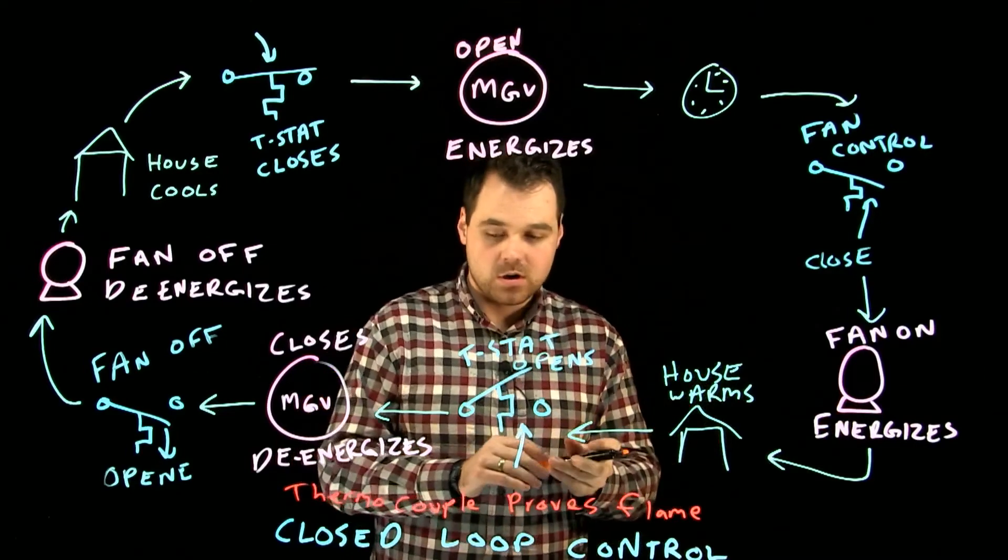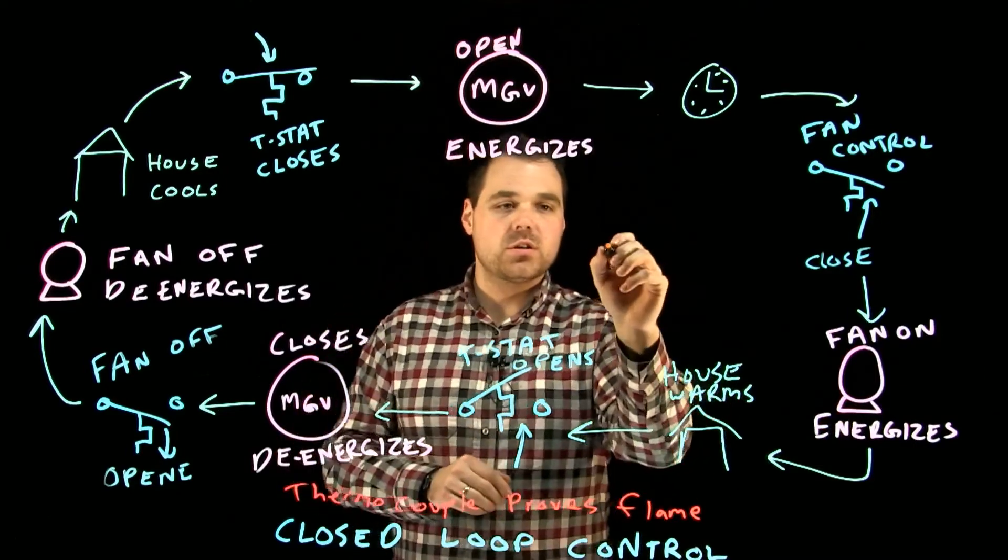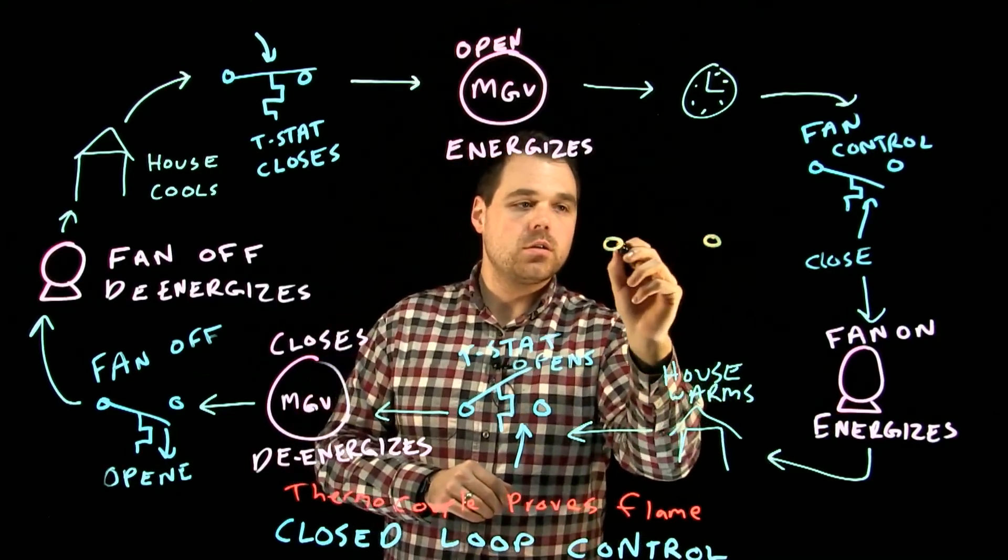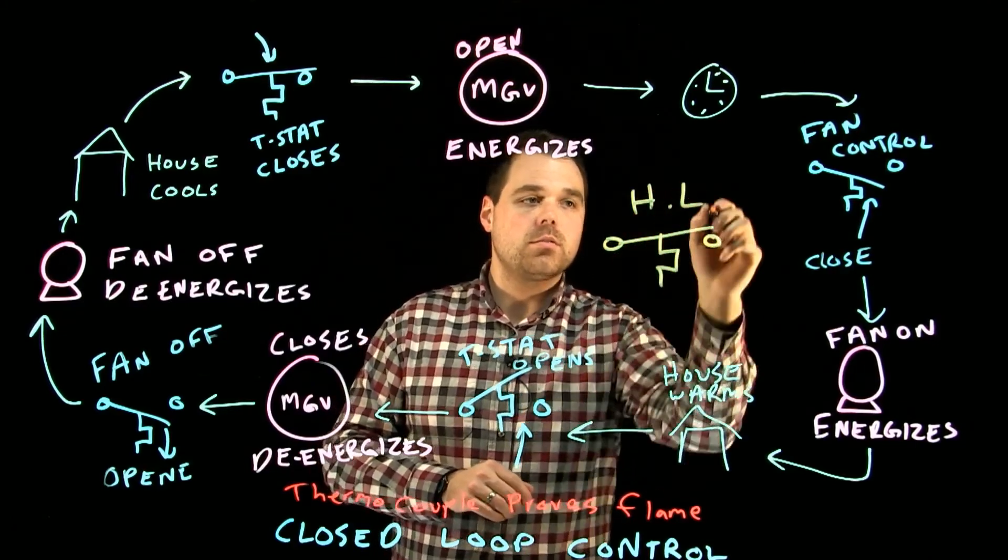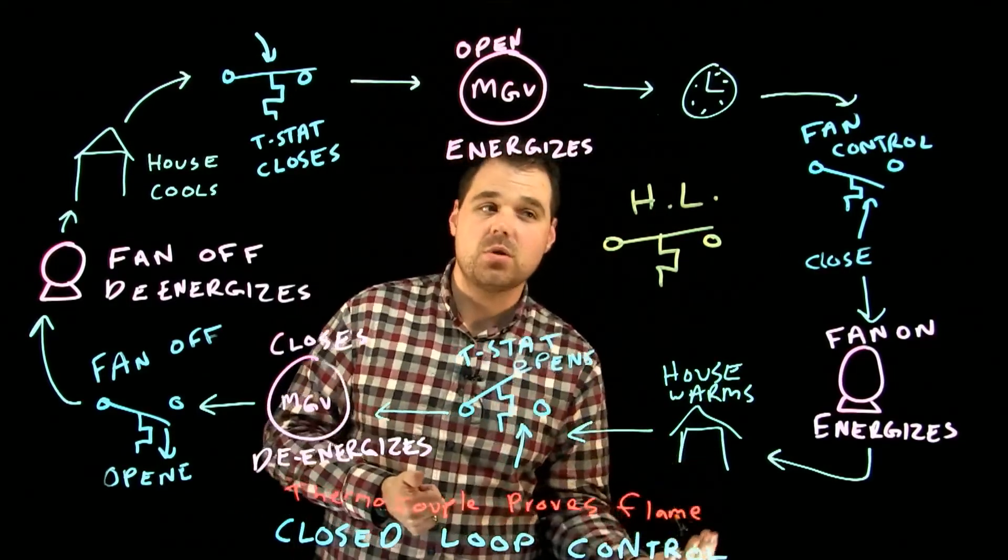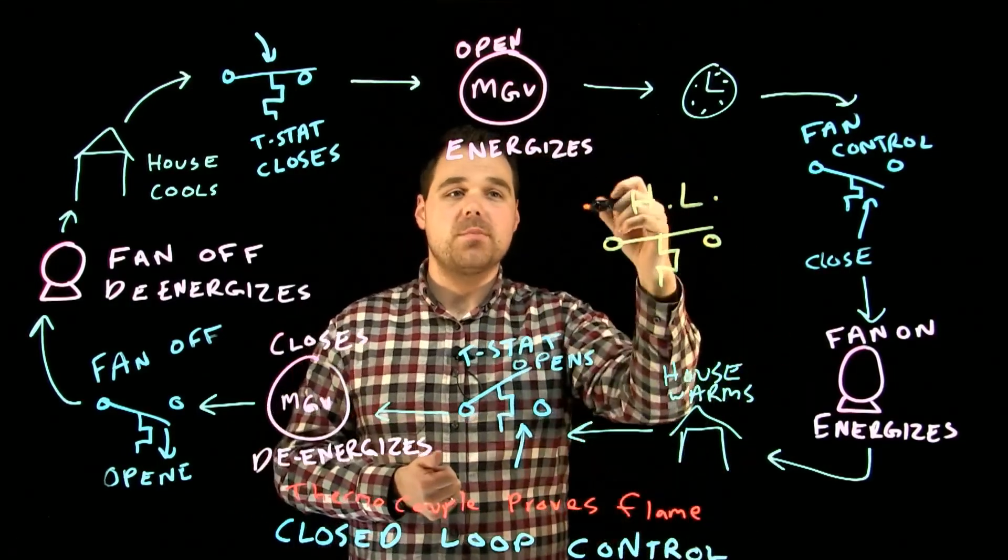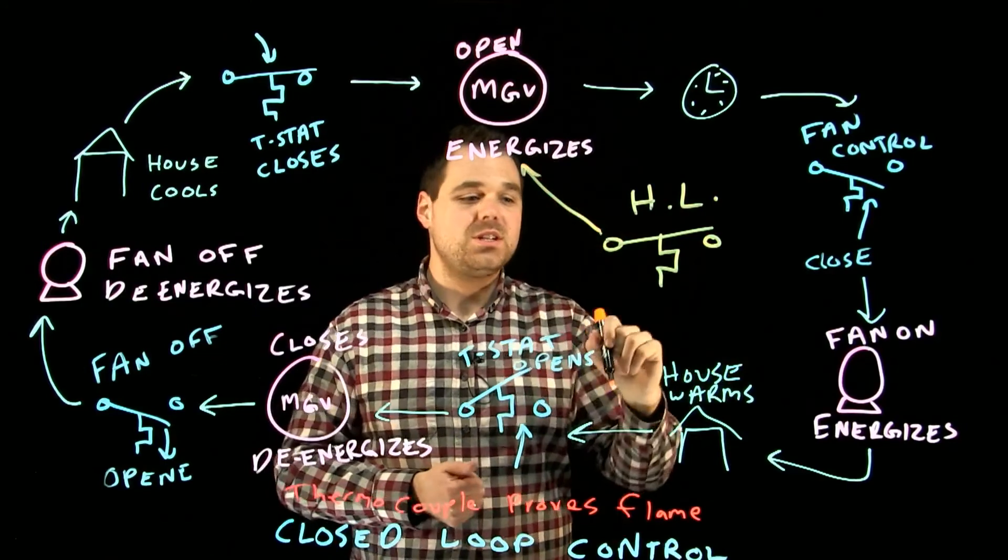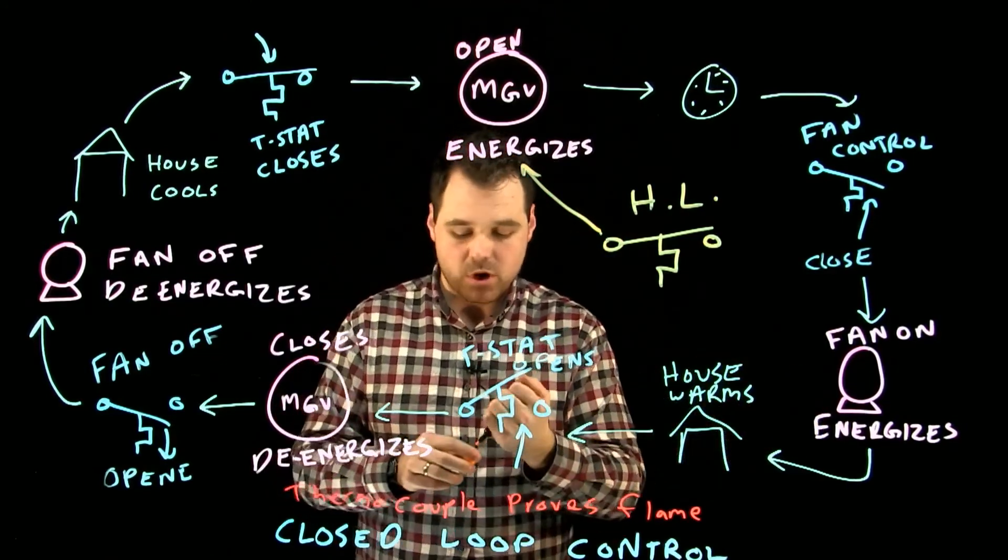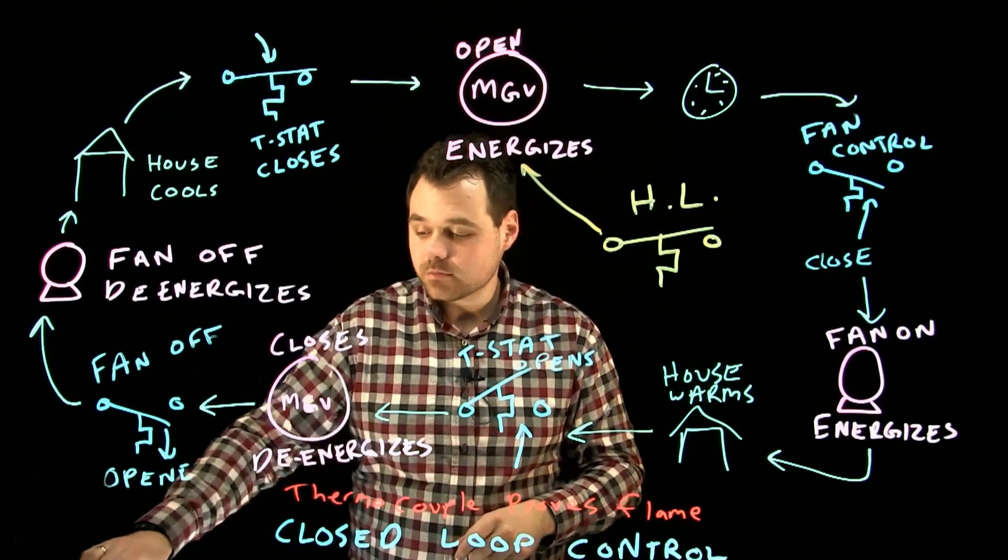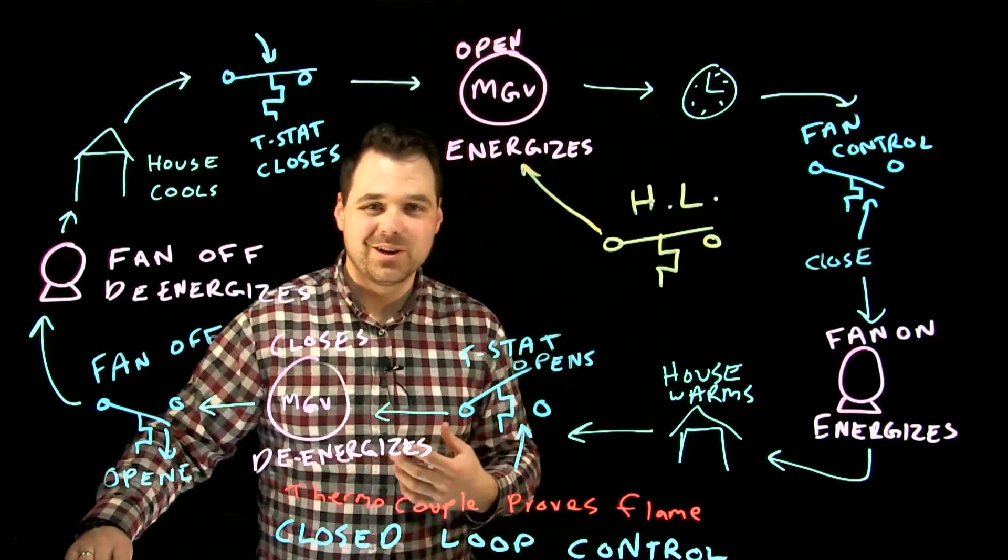The last thing to keep in mind is that all along the process, we have our high limit switch. The purpose of that high limit switch: if it does get too hot in the plenum, it's going to open up and de-energize that main gas valve, but allow that fan to keep running. I hope this was helpful. Please watch the rest of the videos.